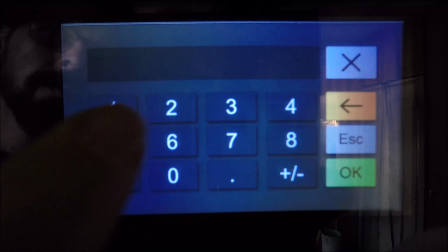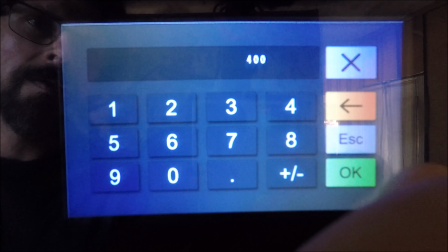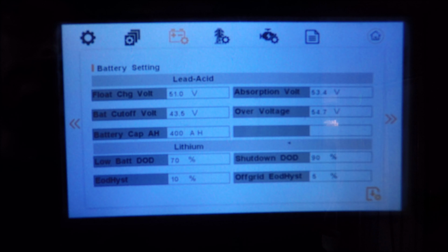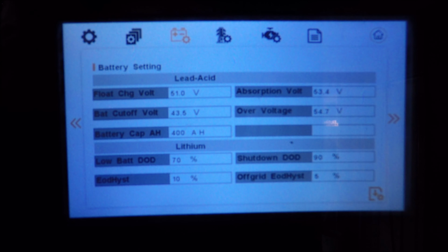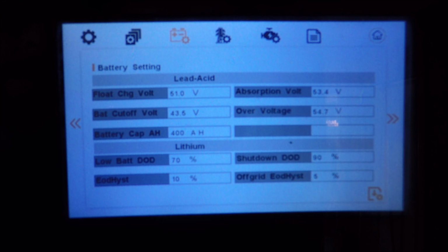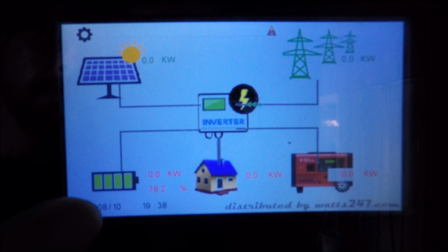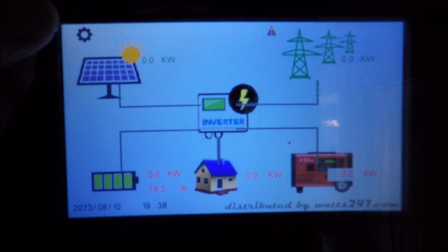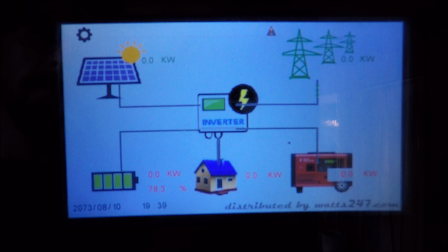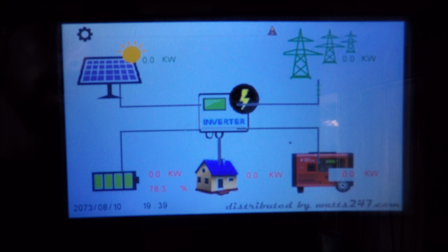and since we have 4 batteries, we're going to set our battery capacity to 400 amp hours, and we're going to hit save. Now this is for my specific battery bank. Like I said, I have 15S batteries that produce 48 volts instead of the 51.2 volts that you may be familiar with. And save. Now we'll go back to the main screen, and you'll see that the error for battery communication has been cleared. We have a 78.2% battery charge, and I'm going to check that with the charge state on the LCD screen on my battery.